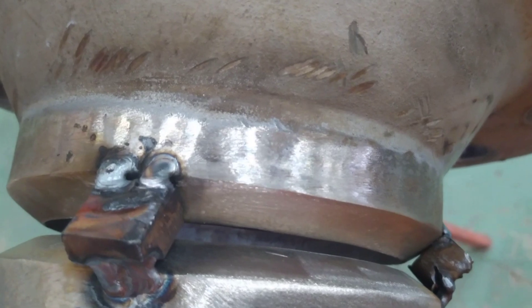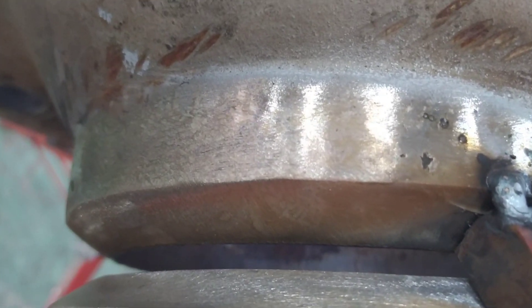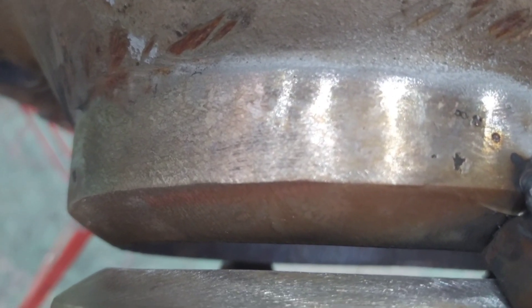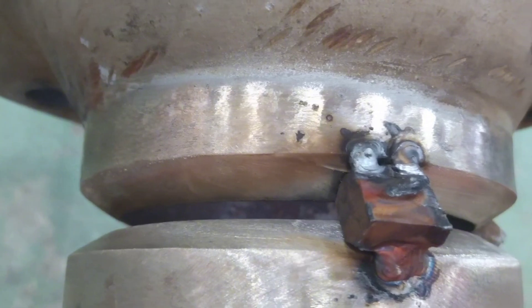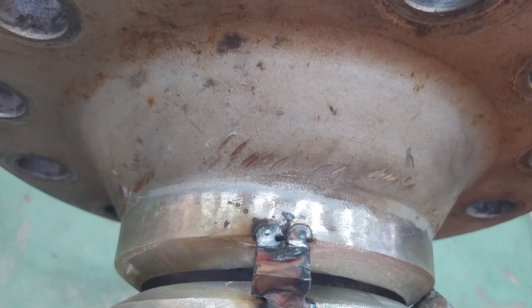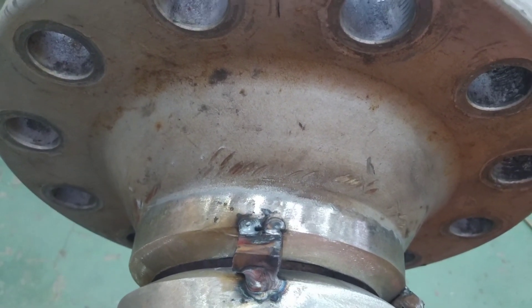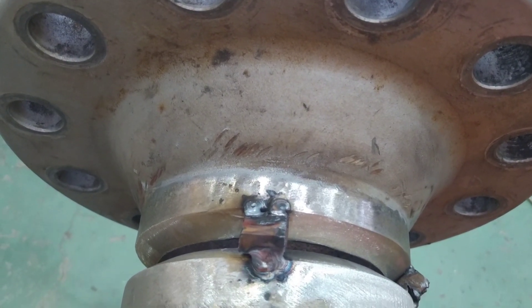During fit-up, gaps are opened between the pipe fittings to be welded, approximately 3-4 millimeters. Having this 3-4 millimeter gap is for better root welding. Depending on the thickness of the wall of the pipe fittings, this 3-4 millimeter gap decreases after welding. Approximately 1-1.5 millimeters remains.